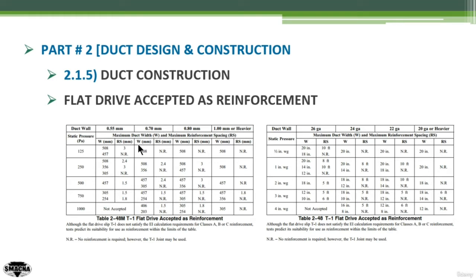Each of these thickness values has two sub-values below it: W in mm and RS in mm. W is the maximum duct width and RS is the maximum reinforcement spacing. So for each value of the static pressure at a certain duct wall thickness, you will have the maximum allowable duct width and the maximum reinforcement spacing.